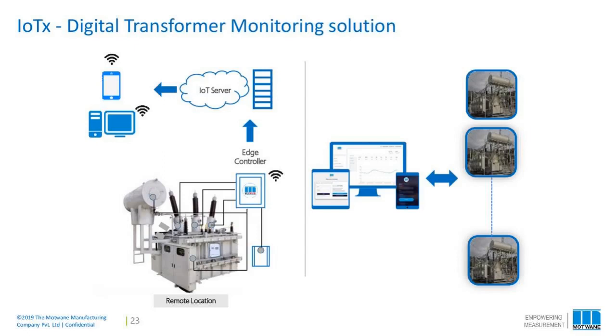On some, it's the basics: oil temperature, winding temperature, oil level, current and voltage. Some were also capturing relay information, when certain relays have been alarmed or tripped, and what conditions led up to that point.